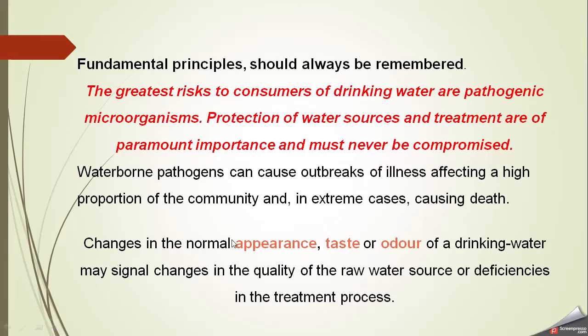Changes in the normal appearance, taste, or odor of drinking water may signal changes in the quality of the raw water source or deficiencies in the treatment process. If water appears dirty or more turbid than normal, something is wrong — either the source is contaminated, the treatment process is not working properly, or there is some mixing occurring in a borehole.